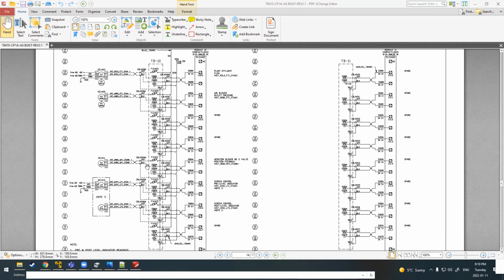There's a couple of different ways to wire 4 to 20 milliamp inputs. You don't really need to know that. Just be aware of it for your future selves. You'll see here, this device, because it receives its own external power, has enough power to power its own loop. So it does not need power from the panel.